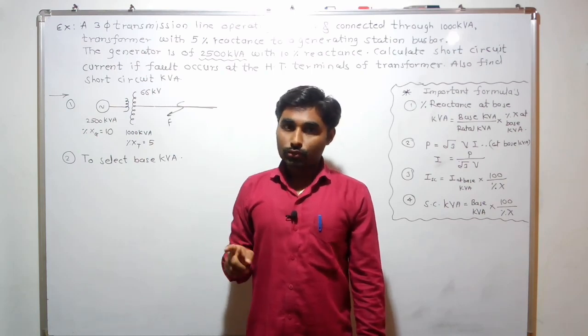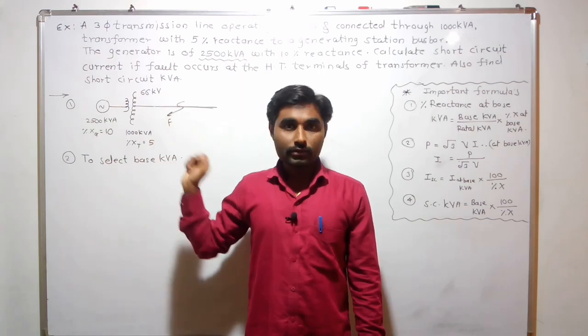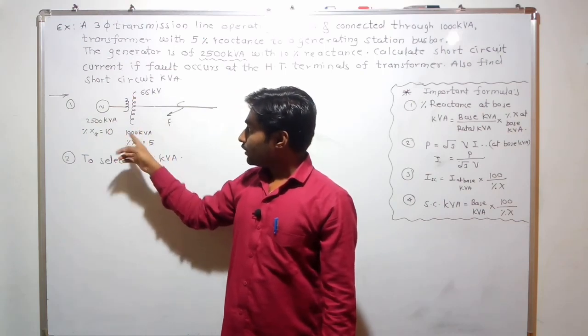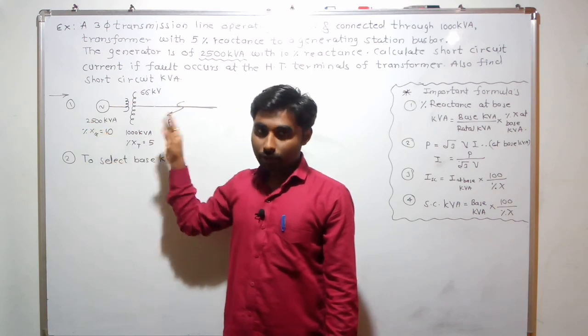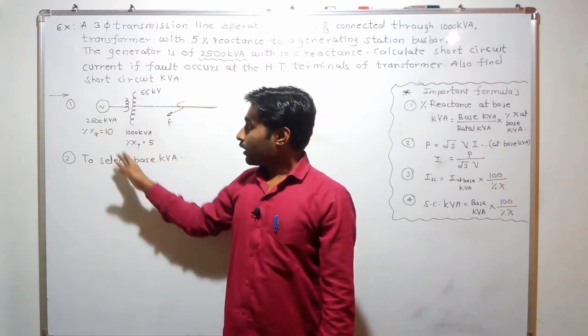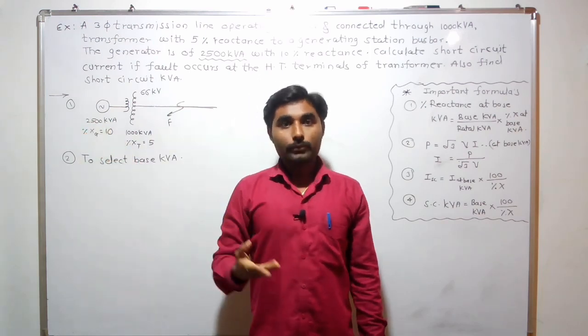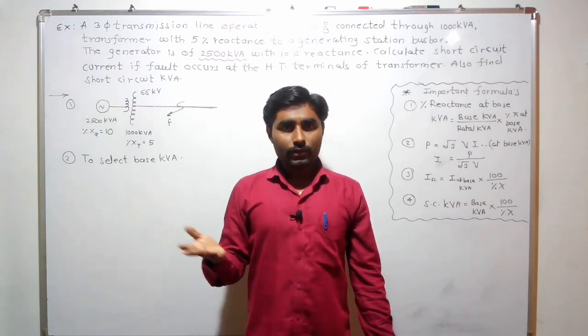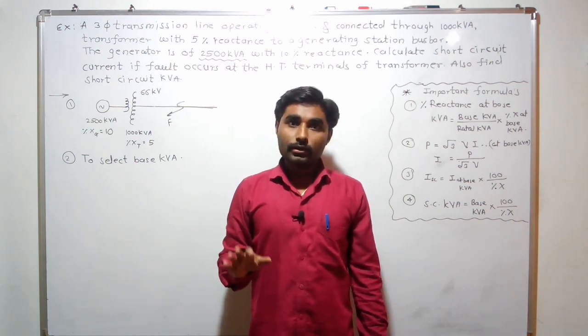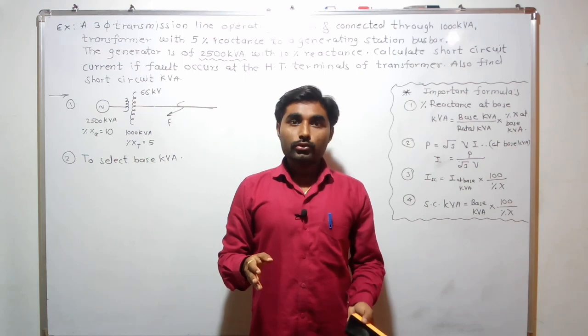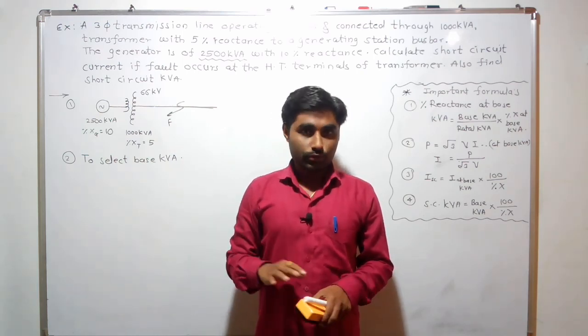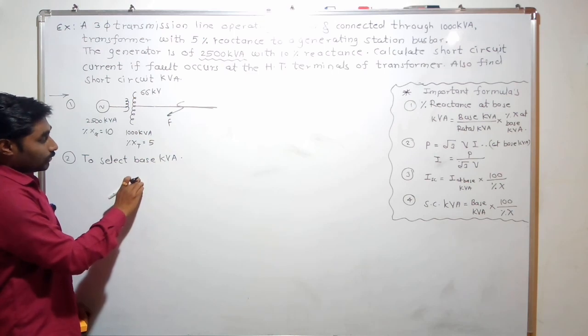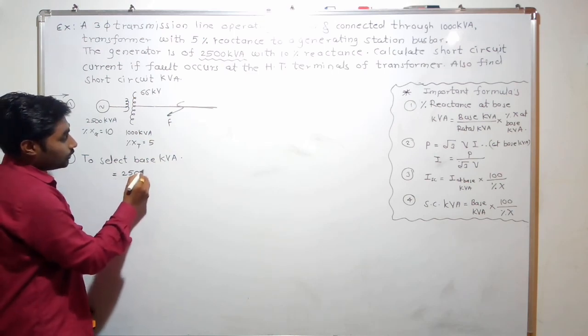The third method is you can choose any arbitrary value such as 4000 kVA or 4500 kVA, but you have to use it throughout the example — you cannot change the base kVA once chosen. In this example, we will select the base kVA as the largest value in the circuit, which is 2500 kVA, the same as the generator rating.